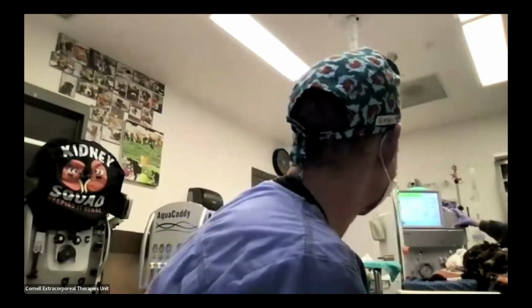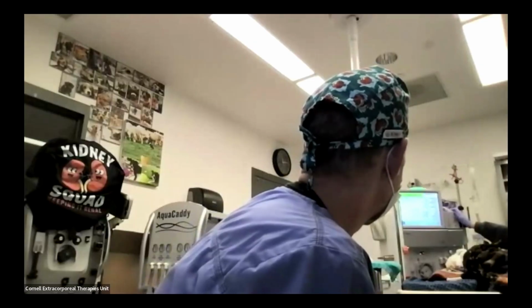So, even right now, our TMP is climbing to 80, 90 once I put that pressure sensor on. And the tubing isn't kinked on the venous side? Like the line through the clamp, and that's all okay? Which is crazy on the Blue Star too, I don't know if you know this, but you can actually take that line completely out of the air detector clamp, the venous clamp, if you're worried that the venous pressures are high, just to make sure that that's not the issue. Obviously, you have to watch really closely that no air is in that line, but you can temporarily take it out and see if that helps at all.